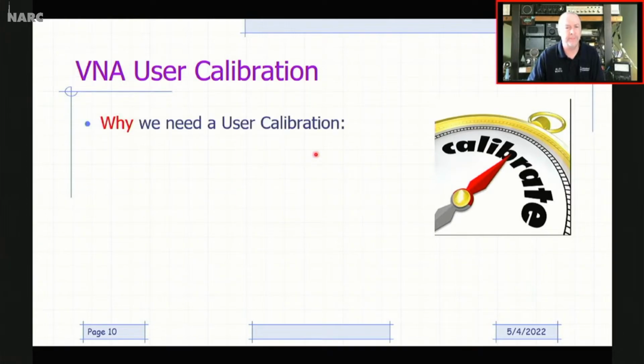Well, there's a couple of reasons for that. Number one is a VNA has generally a very large measurement dynamic range. What I mean by that is it can measure the response of, say, a filter that might have very little insertion loss, like 0 dB of loss or close to 0 dB of loss, but might have 60 or 70 dB of rejection on either side of the passband. That's a really large dynamic range, right? 60 dB is a factor of 1,000,000. So any errors that might creep in due to leakage paths and imperfections in the device will affect the ability to measure this very large dynamic range. So part of the user calibration is to remove those systematic errors so that we can get down to this measurement dynamic range, which can be quite good.